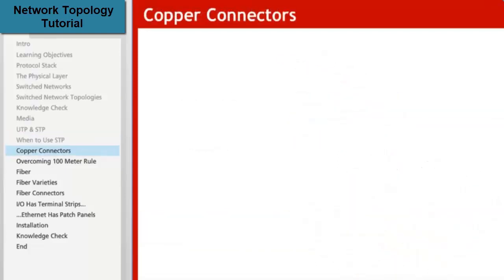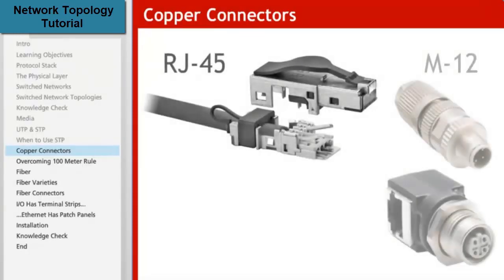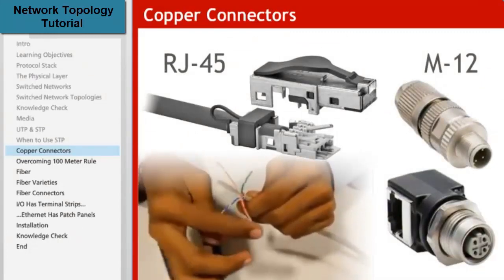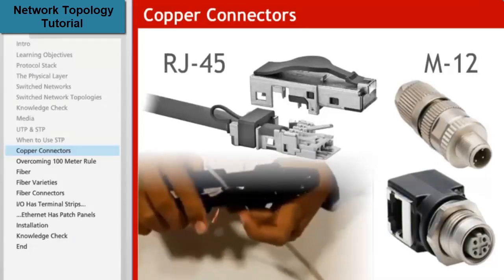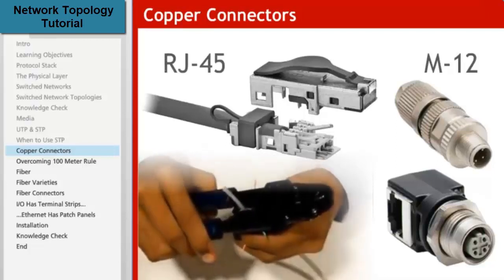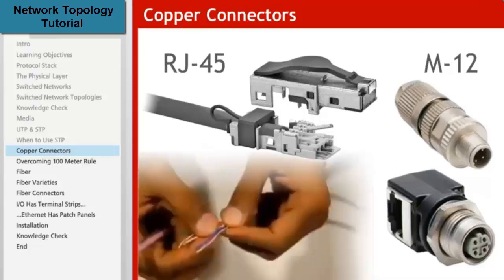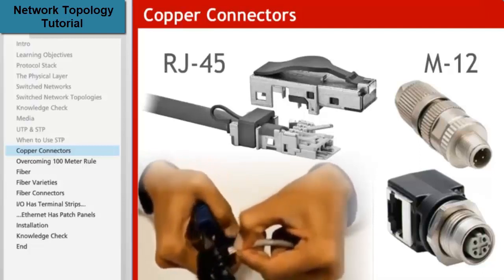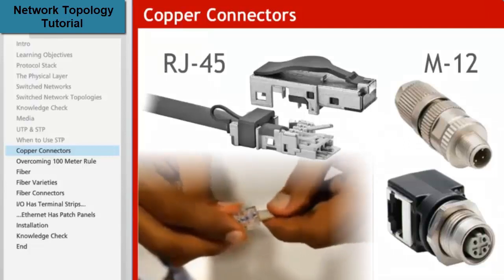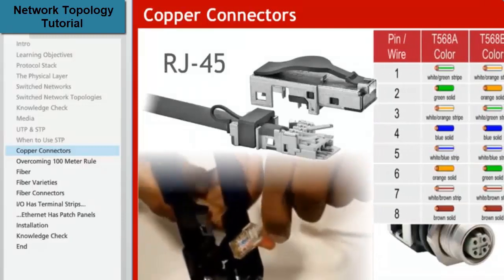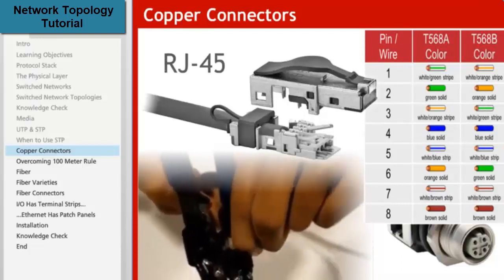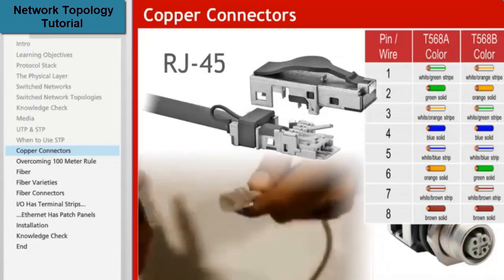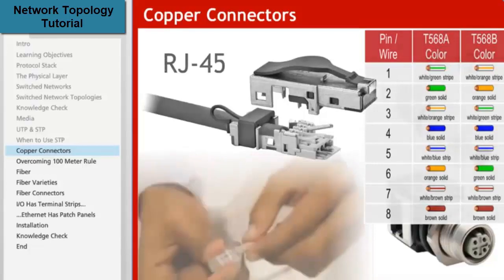Both UTP and STP cables are terminated with similar connectors. These connectors are divided into two groups, commonly called RJ45 and M12. RJ45 are the most common connectors and are always found on office grade equipment. Usually these connectors are crimped on the cable using a special tool. Rockwell also sells insulation displacement connectors that can be attached without using crimpers. RJ45 connectors are available for UTP, STP, CAT5E and CAT6 cable, stranded and solid wire. In some technical literature, you may find that RJ45 connectors are also known as 8P8C, standing for 8 position, 8 contact. Either the T568A or T568B pinouts are acceptable, with both ends of the cable wired the same. The B standard is the most prevalent. A crossover cable used to connect two devices without a switch is terminated as A on one end and B on the other.